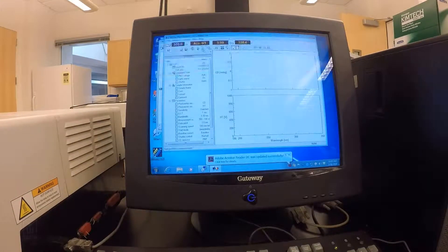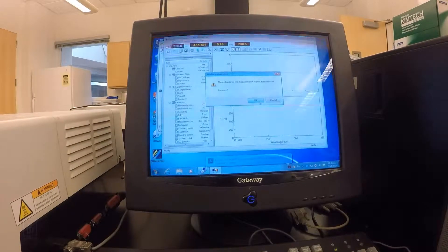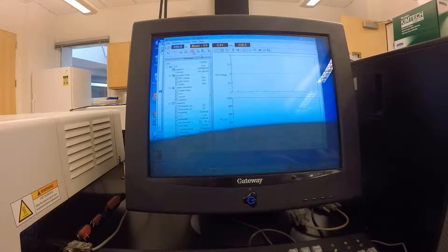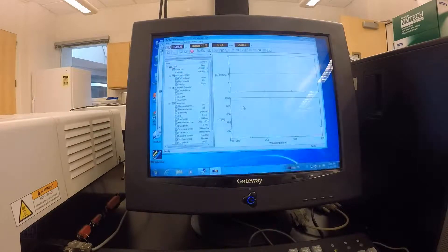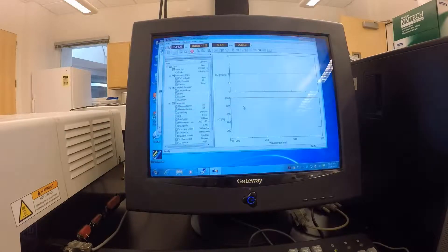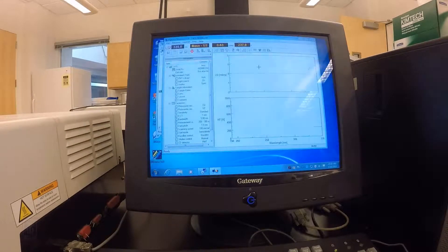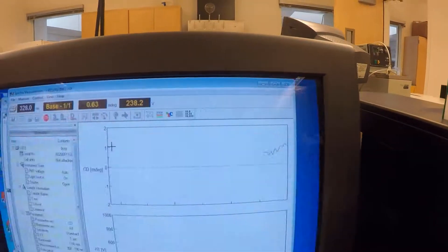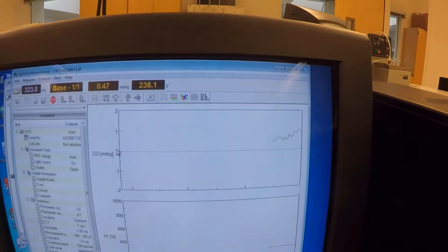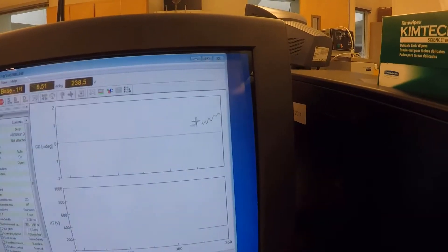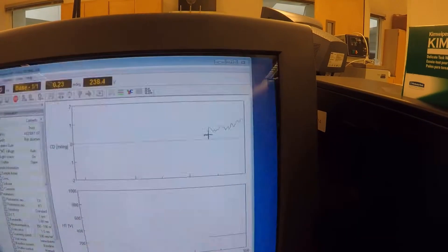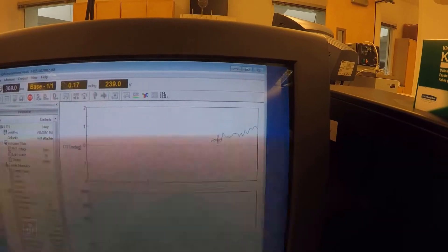For software, it's already set up from our method, so I just need to hit baseline measurement. If you look here, we're starting to see some change in circular dichroism, but it's on the very small scale. This is between zero and two milli degrees of circular dichroism. So this is a very flat line. It's just showing all the bumps and lumps right now as it scans through. But when we subtract this out, it will essentially be subtracting a flat line. You just want to let this thing scan through.